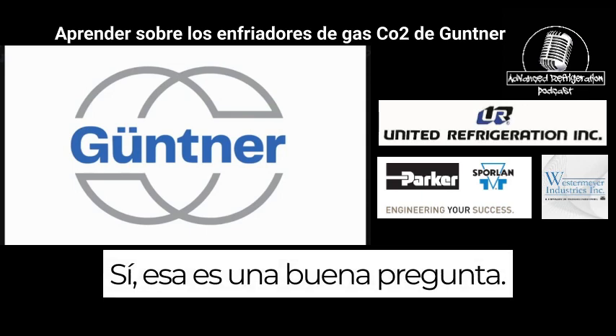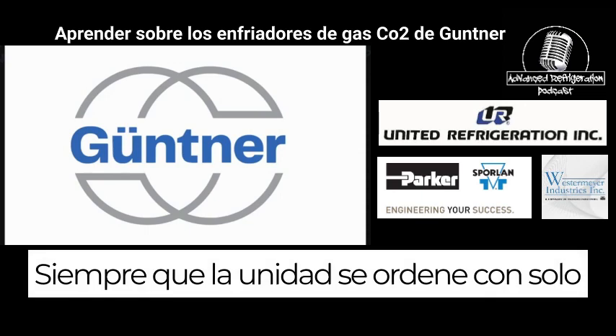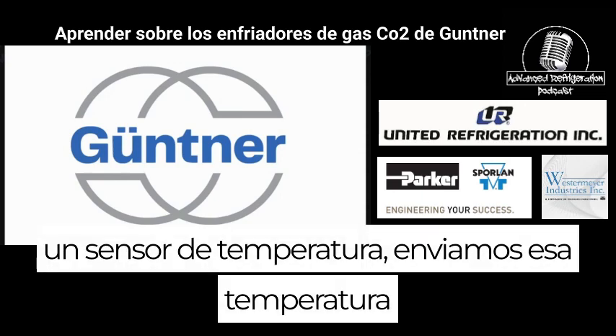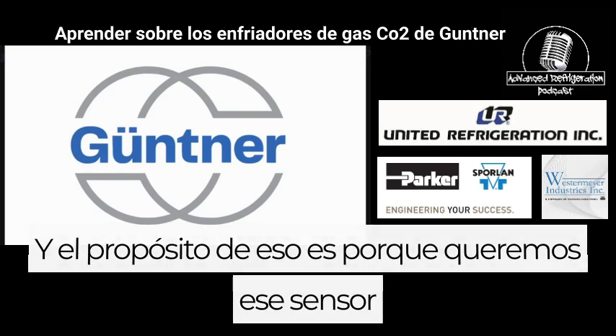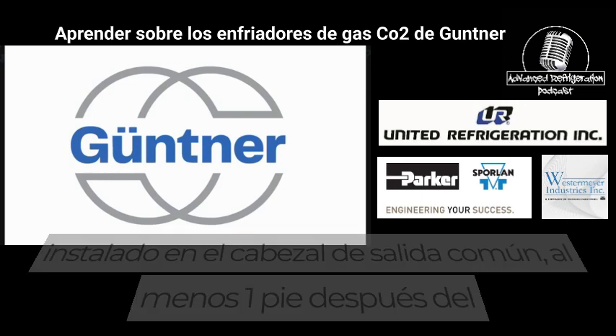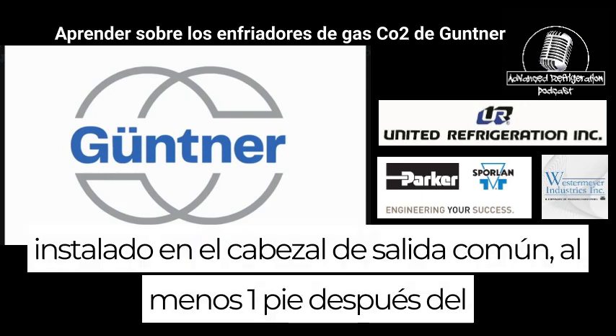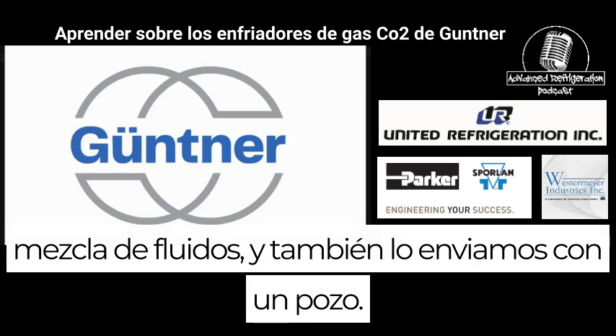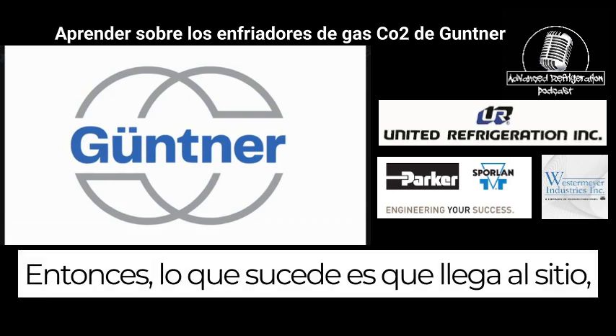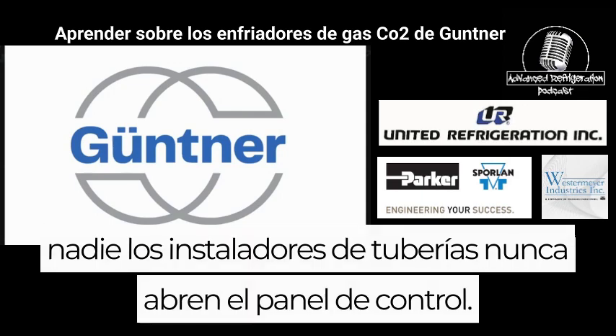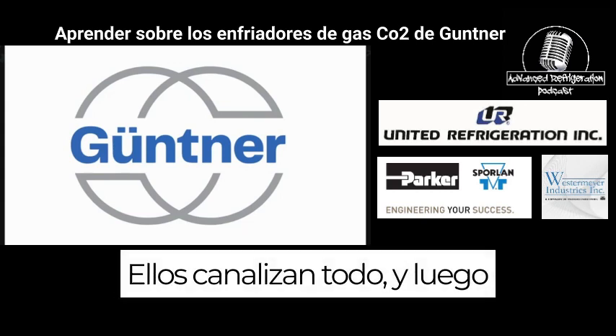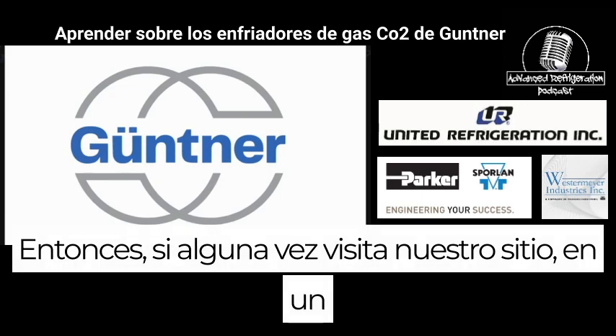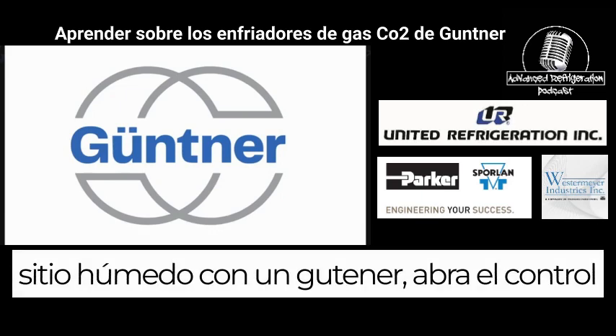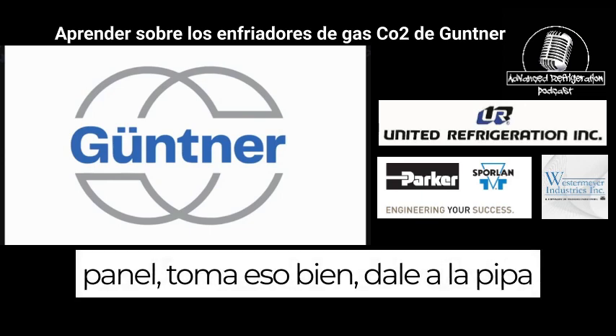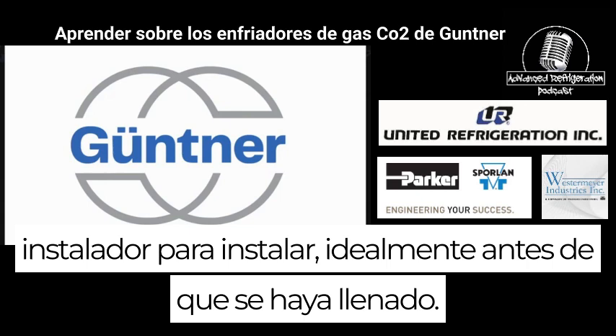Yeah, that's a good question. Whenever the unit is ordered with just one temperature sensor, we ship that sensor inside the control panel. The purpose is that we want that sensor installed in the common outlet header at least 1 foot after the fluid's mixed. We also ship it with the well. What happens is it gets to the site, the pipe fitters never open the control panel, they pipe everything up, and then the sensor is not installed. So if you're ever at a site with a Guntner, open up the control panel, take that well, and give it to the pipe fitter to install, ideally before the system's been filled.